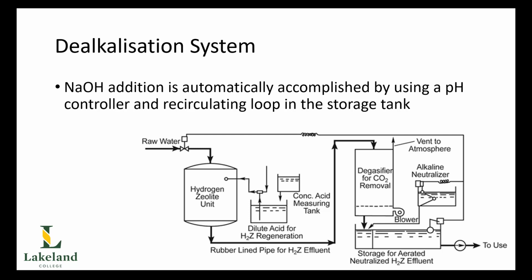So you can think of it, very oversimplified, as we're changing out the bad alkalinity that will break down and cause our carbonic acid and CO2 release, and we replace that with a better alkalinity that won't cause us issues, putting in our hydroxide alkalinity. There's a lot more to it than that, and you'll get into this more as you move on and do your second class. But at third class level, we can kind of get away with simplifying it like that.